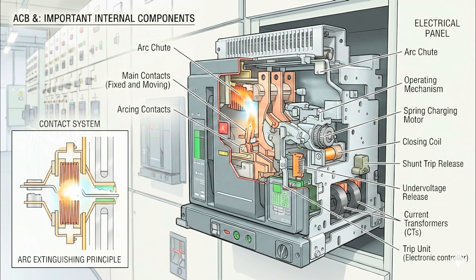Always remember, ACB maintenance is very important. Loose connections, dust accumulation, and worn-out contacts can cause serious electrical failure. Always follow safety procedures and isolate power before doing maintenance work on the ACB.